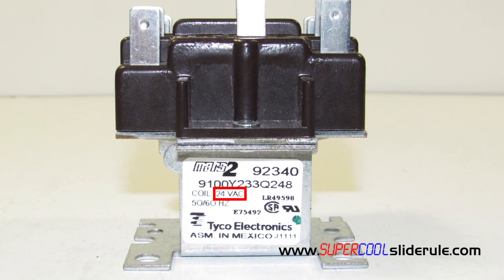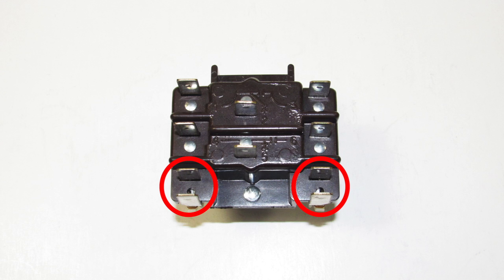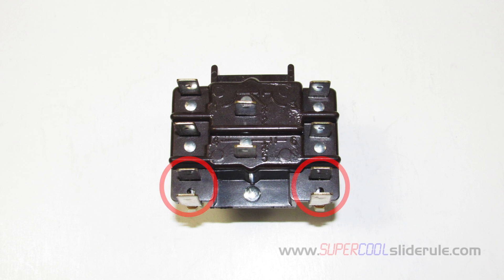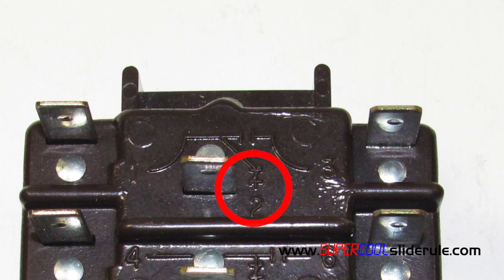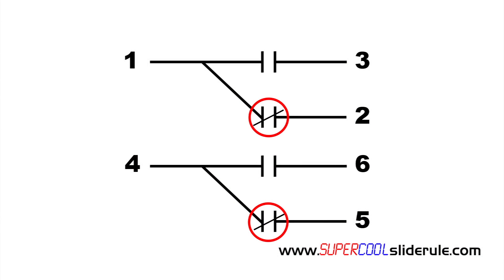When 24 volts is supplied to these two terminals, the relay should switch the terminals that have continuity. The symbols located here indicate that there should be continuity between terminals 1 and 2, and continuity between terminals 4 and 5 in the normal position. Normal position means no electricity is being supplied to the coil.